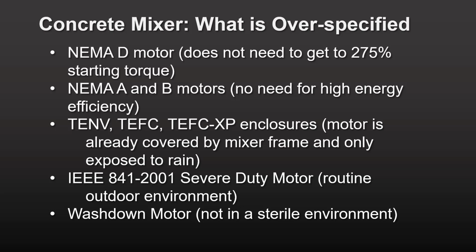The motor is located in a routine outdoor environment, so an IEEE 841-2001 severe duty motor would be overkill. Construction site is anything but a sterile environment. There's dust everywhere, so a washdown motor is certainly not needed.